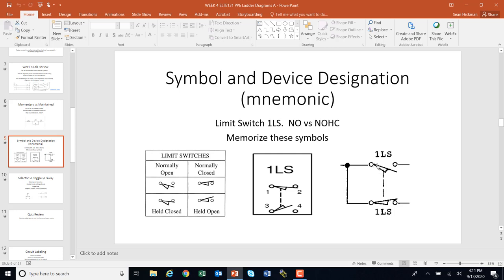If you have this limit switch on one rung and then many pages later use that same limit switch again, there might be an arrow on it with a number. Let's say this was rung one, and the arrow says 90 — meaning on rung 90 later, a related contact changes. The dashed line with an arrow and a number means you have to look further into the ladder logic, because when this contact closes on rung one, that's going to affect something on rung 90. That's how the arrow with a number ties two contacts together when it's not obvious they're working together.